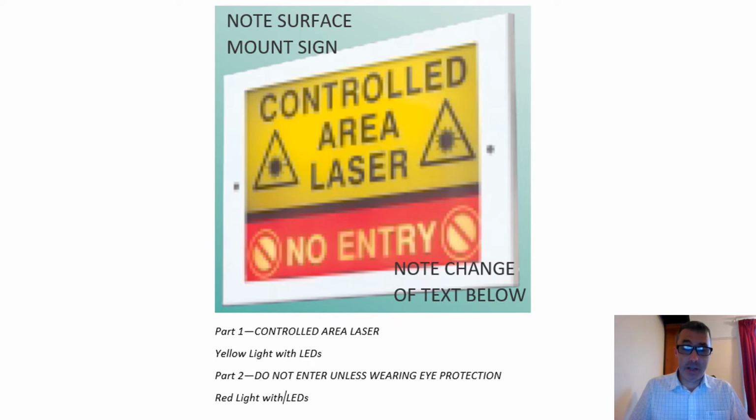And the red section here, we're suggesting a change of text: do not enter unless wearing eye protection, which would match the plastic signs that are on the doors. So the red section may only be illuminated when the laser is actually firing, but in some cases that could be on all the time, and that would effectively mean that nobody enters the theatre at any time. And certainly if you've got this text here, do not enter unless wearing eye protection, you would want that red section to be displayed all of the time.